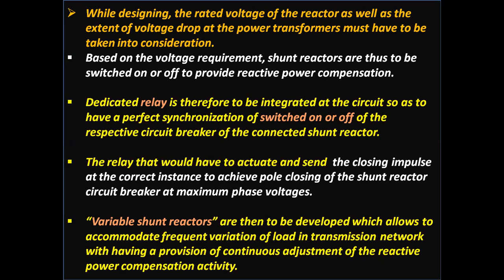While designing the rated voltage of the reactor, as well as the extent of voltage drop at the power transformers, must be taken into consideration. Based on the voltage requirement, shunt reactors are thus to be switched on or off to provide reactive power compensation.